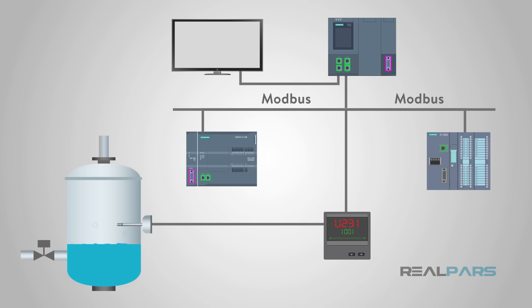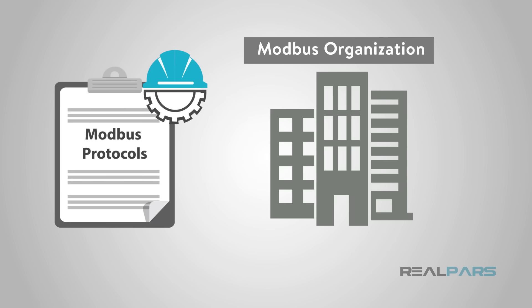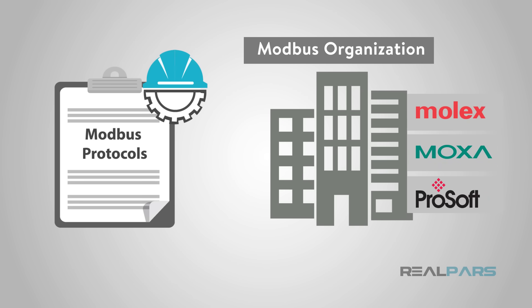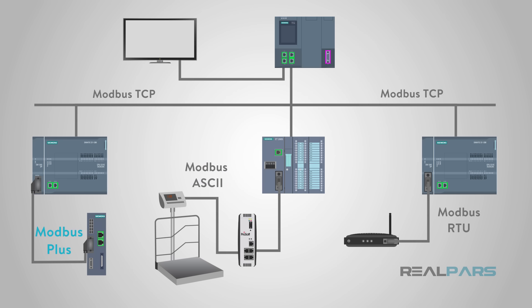Modbus provides a common language for devices and equipment to communicate with one another. For example, Modbus enables devices on a system that measures temperature and humidity connected on the same network to communicate the results to a supervisory computer or PLC. The development and update of Modbus protocols are managed by the Modbus Organization, an association of users and suppliers of Modbus-compliant devices. Several versions of the Modbus protocol exist for serial port and Ethernet, and the most common are Modbus RTU, Modbus ASCII, Modbus TCP, and Modbus Plus.